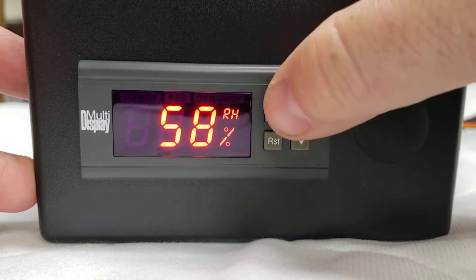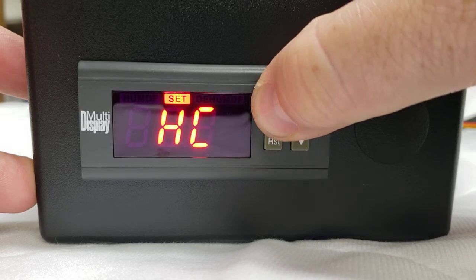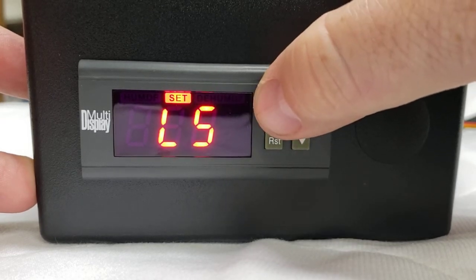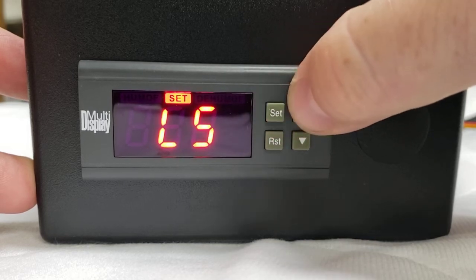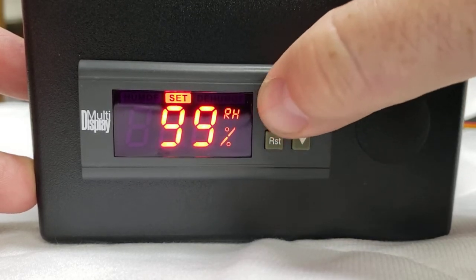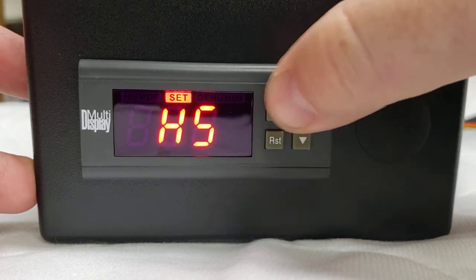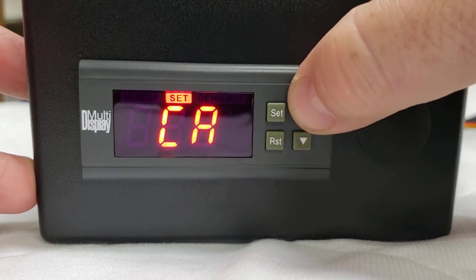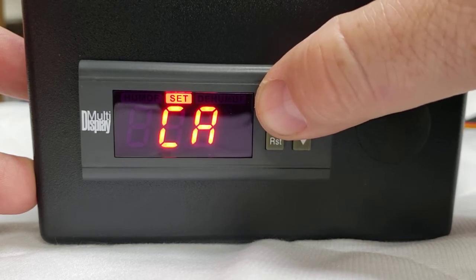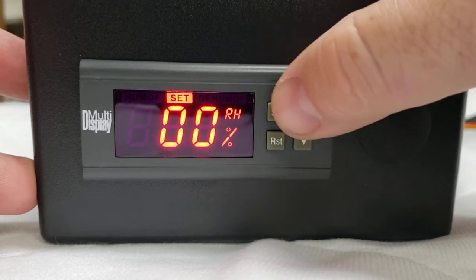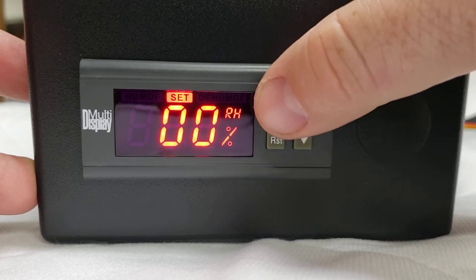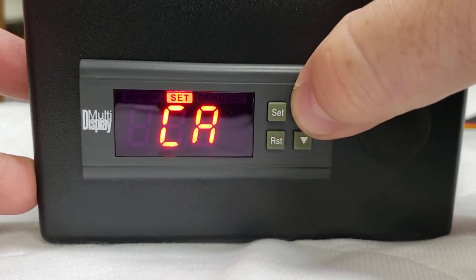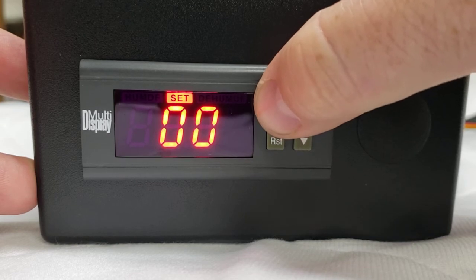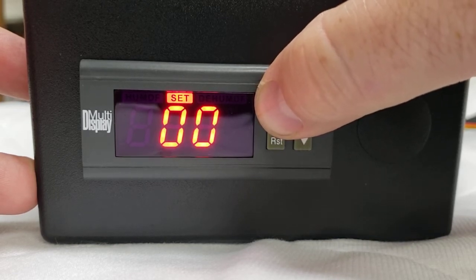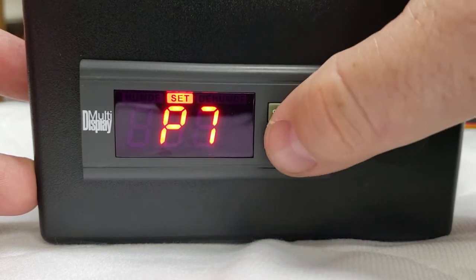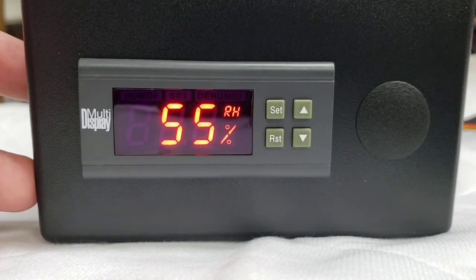Then go back into the internal settings here. The LS is a limit set. We really don't need that set, so it can be at 0, 1. Up arrow to get to your HS, that can be at 99. Set takes us back again. Up arrow to CA, that's a calibration in case the sensor gets off from the internal reading of the unit. We assume it's calibrated perfectly, so we set it to 0% calibration. And then delay time is a delay before your pump would kick on. We don't want any delay here, so we're going to set that to 0, 0. Now, reset will take us back to the main screen.